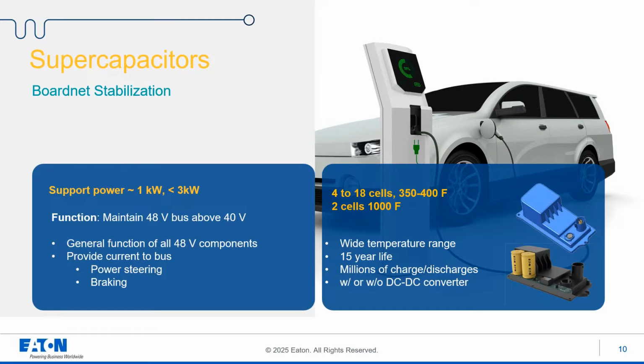There are different approaches to the supercapacitor design. In some cases, the supercapacitors are sized to support a maximum power level and discharge time with no DC to DC converter. But most designs use a DC to DC converter to utilize the capacitors more fully, or to reduce the number of supercaps and boost the voltage to the required level. So we can see anywhere from 4 to 18 cells in the 350 to 400 farad range, although we have seen some designs that might use just 2 cells but at 1,000 farads. It really comes down to a balance of power, energy, and of course size and cost.